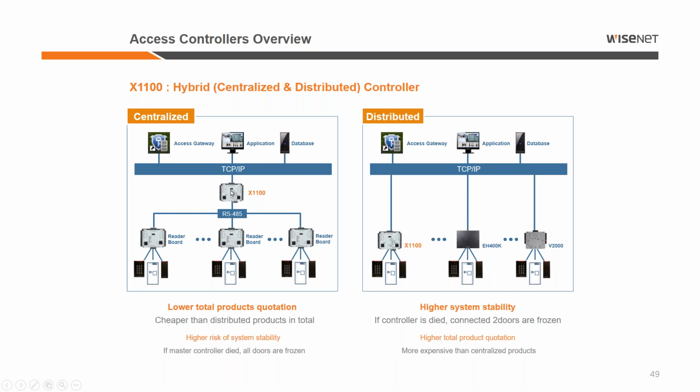So if there is any disconnection, then of course, it will not be able to speak. For example, if this point is disconnected, then this controller is out of the network. If this point is disconnected, then this controller is out of the network. So this is the challenge. If there is one more controller here, once this wire is disconnected, every other controller cannot speak to the master controller because the wire was disconnected. It's not something that happens often, but it is the design.